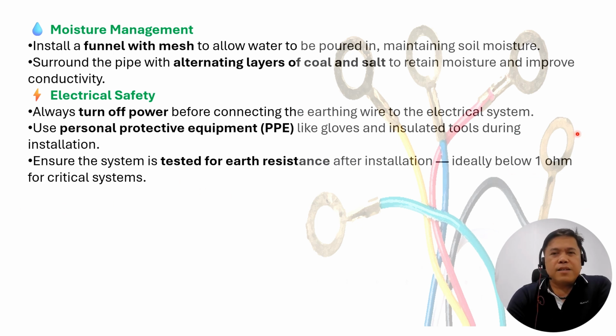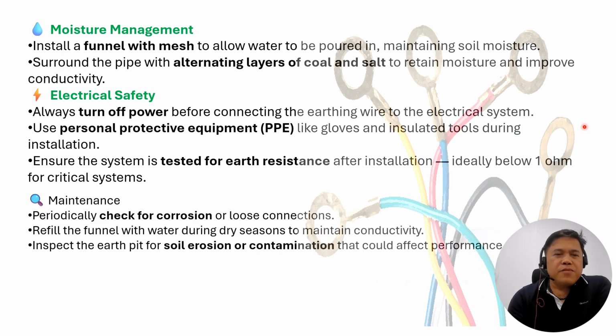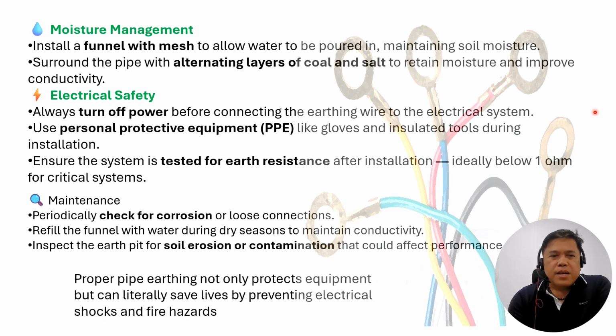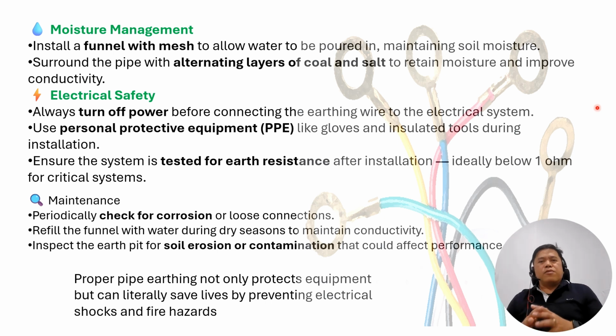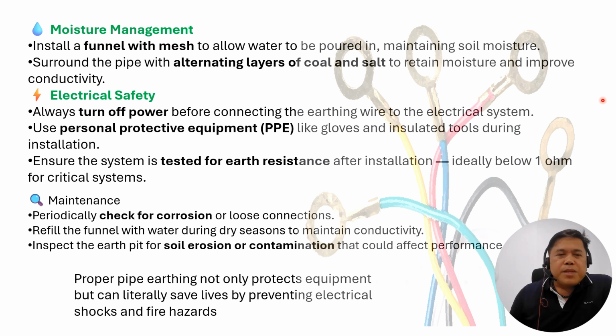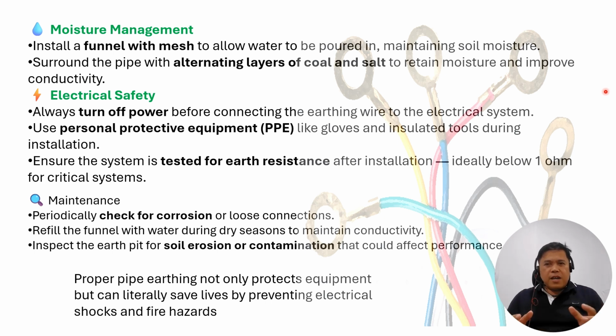So maintenance: periodically check for corrosion, refill water during the dry season, inspect the earth pit for soil erosion and contamination that could affect performance. Proper pipe earthing not only protects equipment, but can literally save lives by preventing electrical shocks and fire hazards. So guys, this is important.